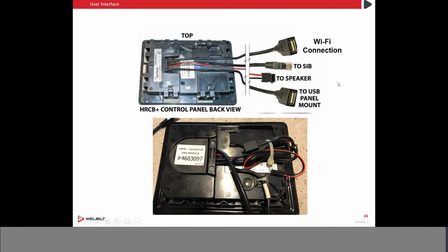If that front USB port on the front control panel has grease in it, don't try to stick a USB stick into it. You're going to end up with a damaged USB stick, or you're going to say, hey, the USB is not taking the programming correctly, etc., because it's not recognized. Well, that's because there's probably grease in there. Open the front panel and disconnect this connection that goes to the USB panel mount, and put the USB stick in here, which goes directly into it. Inside the grill, you have less chance of having grease inside this port.